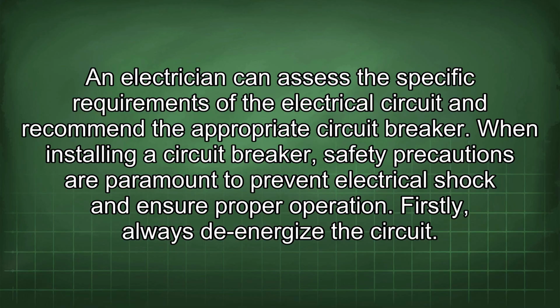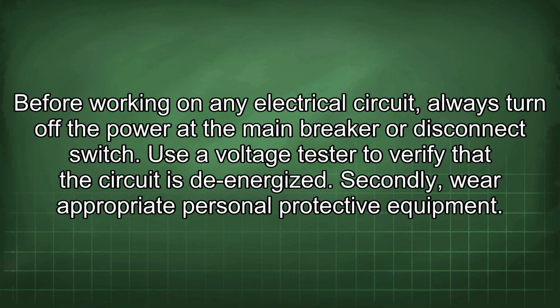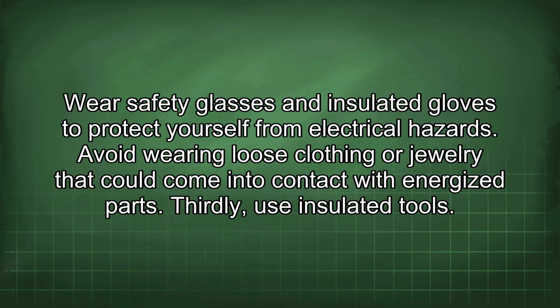When installing a circuit breaker, safety precautions are paramount to prevent electrical shock and ensure proper operation. Firstly, always de-energize the circuit. Before working on any electrical circuit, always turn off the power at the main breaker or disconnect switch. Use a voltage tester to verify that the circuit is de-energized. Secondly, wear appropriate personal protective equipment. Wear safety glasses and insulated gloves to protect yourself from electrical hazards. Avoid wearing loose clothing or jewelry that could come into contact with energized parts.